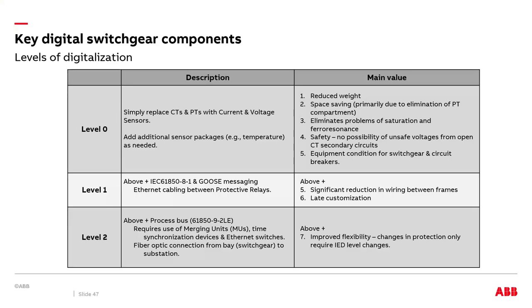The equipment condition is also monitored. So this is like a base level, depending upon how comfortable the design engineer is with introducing digitalization into their own switchgear. So this would be the base level. Now, we could take it a level up if we are comfortable with this and introduce IEC 61850-8-1, which includes MMS, which is manufacturing messaging specification.